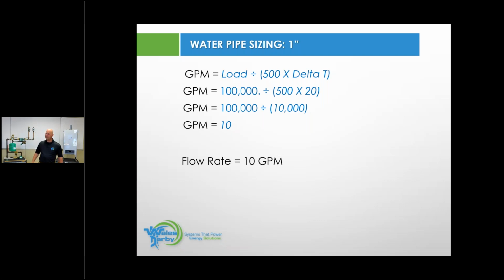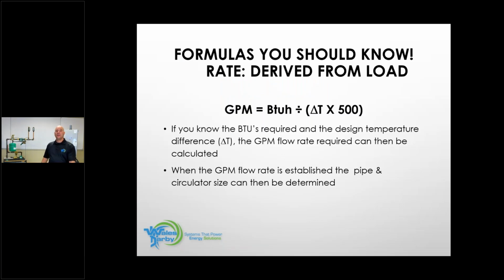Yep. And somebody wants to know, can you go back to the last slide? Absolutely. Right there. If you know the BTU required and the design temperature difference, delta T, the GPM flow rate required can be calculated. So that's either we're going to multiply or divide. When the GPM flow rate is established, the pipe and circulator size can then be determined. So if I have a 1,000,000 BTU boiler or 200,000 BTU boiler, I can't pipe it in 1 inch, and we'll get to a pipe chart here shortly that'll tell you what a 1-inch pipe will carry.